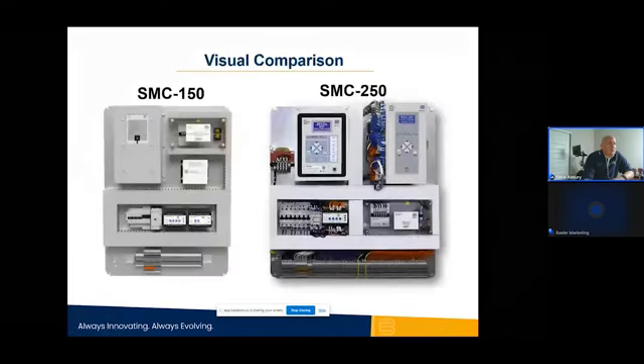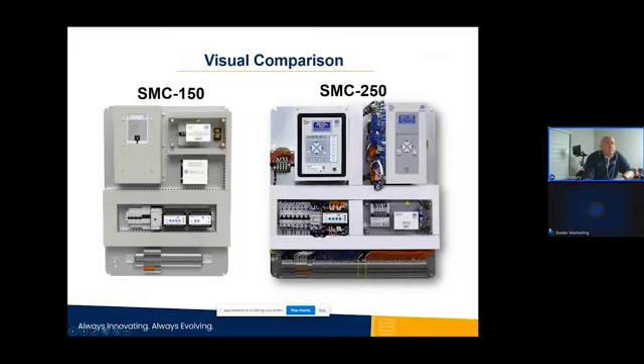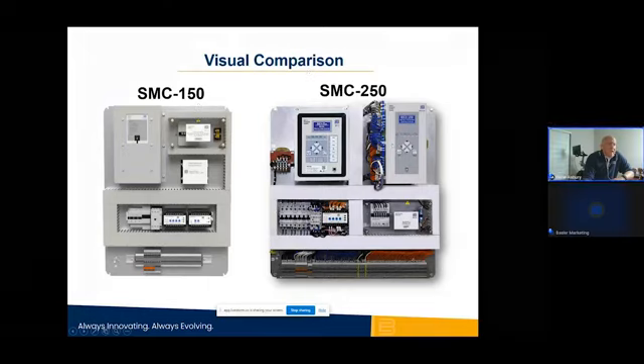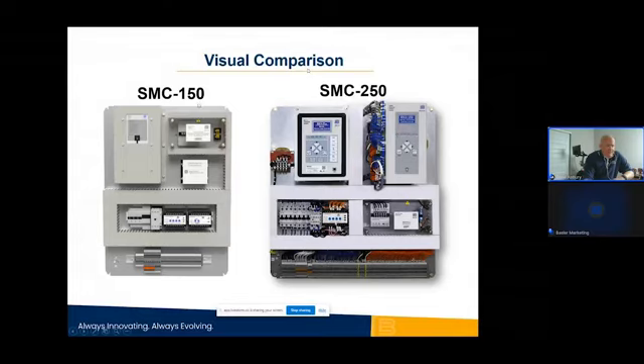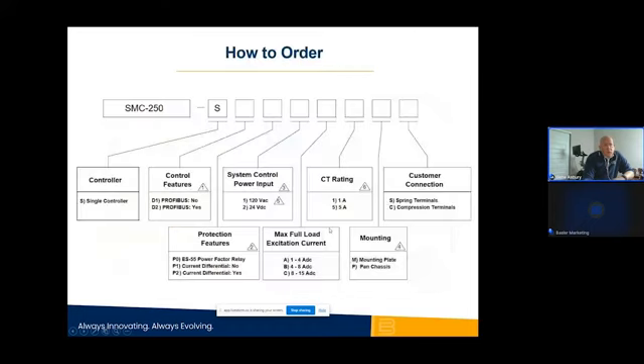And here's some of our pre-engineered panels. The SMC 150, capable of 10 amps continuous, and then the SMC 250 with the optional BE1-11 protection. So that's capable of 15 amps. So you've got some small relays down here, the ES55, and then the ES74, that's your shunt protection for over-excitation and under-excitation protection. We do have an order form for how to order the SMC 250 or the 150. So these are catalog, pre-engineered circuits that have been very popular for us.